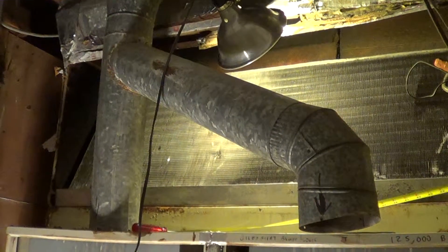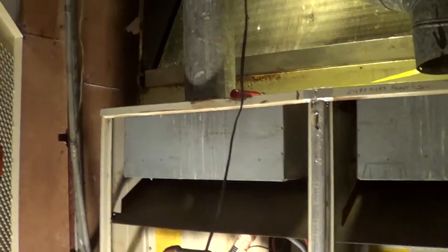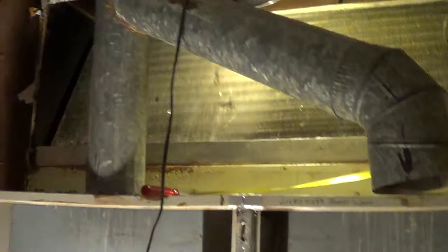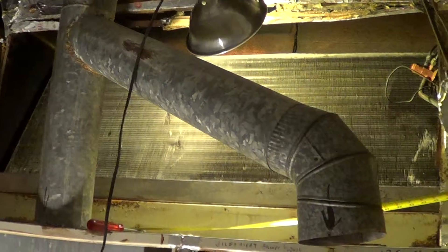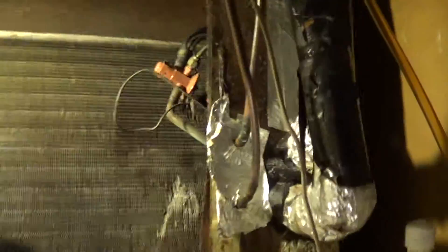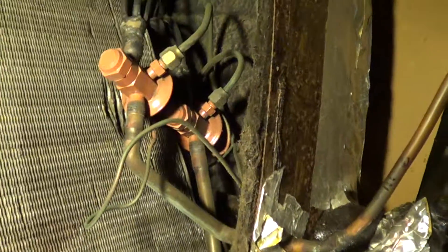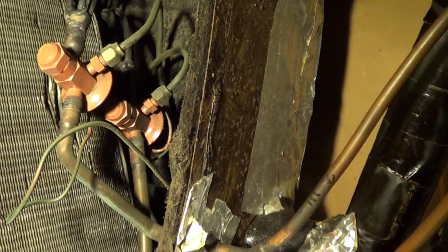This hasn't been taken apart for years. The coil in there is four feet long, and to get it out I had to swing both furnace connections out. These are two 125,000 BTU furnaces from 1985 — they both still work. I wish they would have put two discrete coils you could physically separate, but instead there's one giant four-foot coil that feeds two 5-ton air conditioners. I was out vacuuming the system, and here's the TXV for the two units.